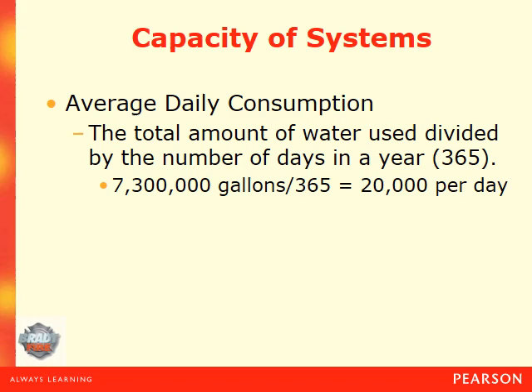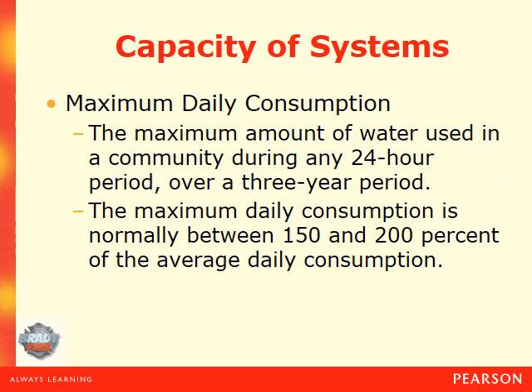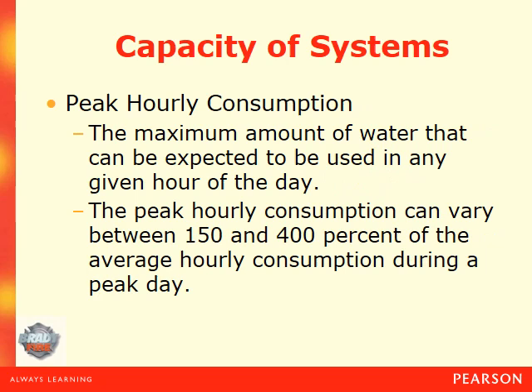Average daily consumption can be figured as follows: the total amount of water used divided by the number of days in the year. For example, 7,300,000 gallons divided by 365 days equals about 20,000 gallons used per day in the municipality. Maximum daily consumption is the amount of water used in a community during a 24-hour period over a three-year period; it is normally between 150 and 200 percent of the average daily consumption. Peak hourly consumption is the maximum amount of water expected to be used in any given hour of the day and can vary between 150 and 400 percent of the average hourly daily consumption during a peak day.